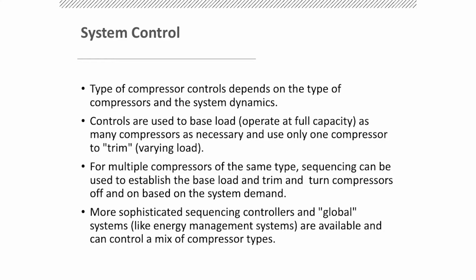Types of compressor controls depend on the dynamics and the way you want to run them. Controls are used to base load. Again, the best base load units should be run at full capacity. It sounds like a no-brainer, but you find a lot of times when you go into any kind of facility, whether it's a building or a plant, what I've found over the years is they're really engineered to begin with and then they just grow. And they change so much over time, nobody keeps up with it.